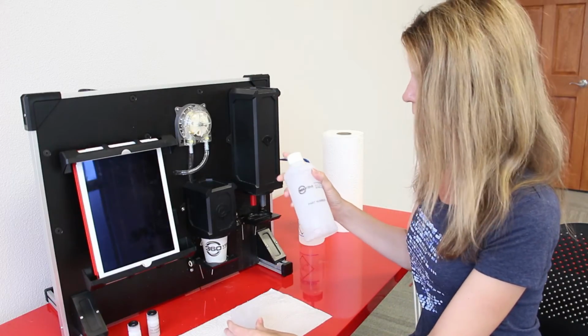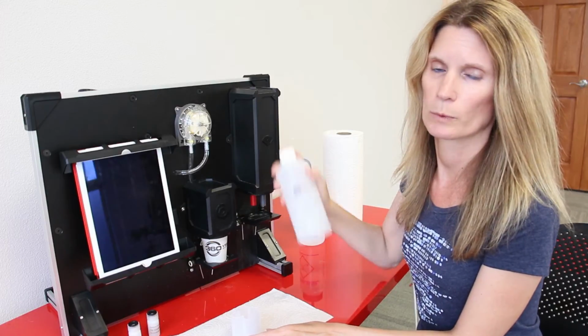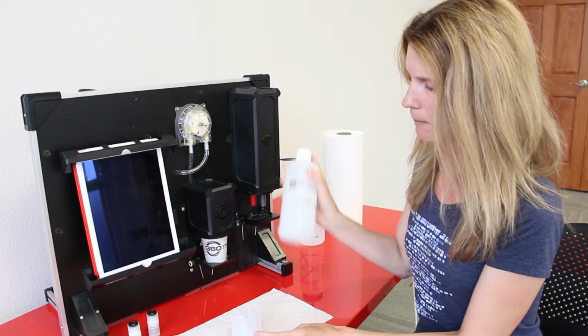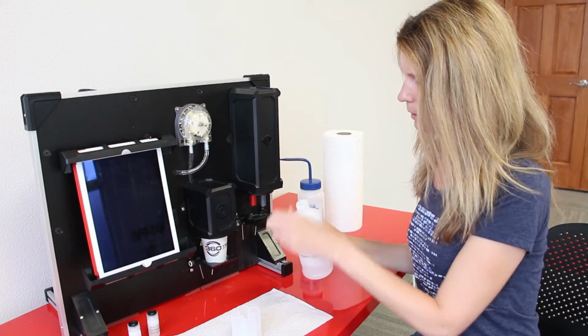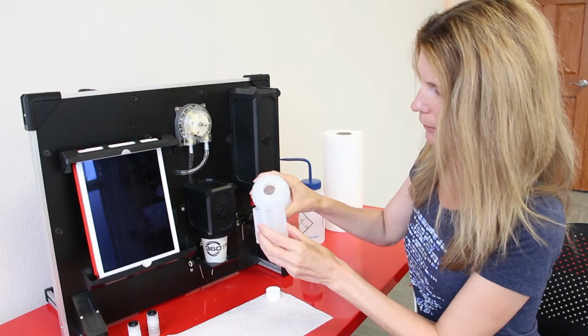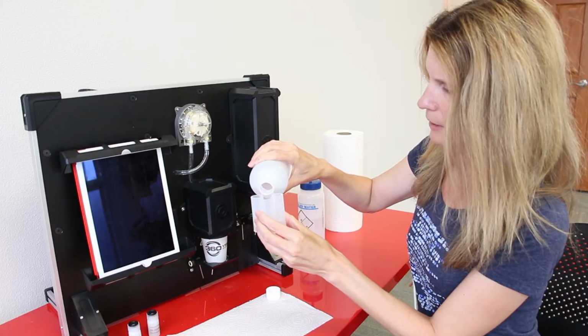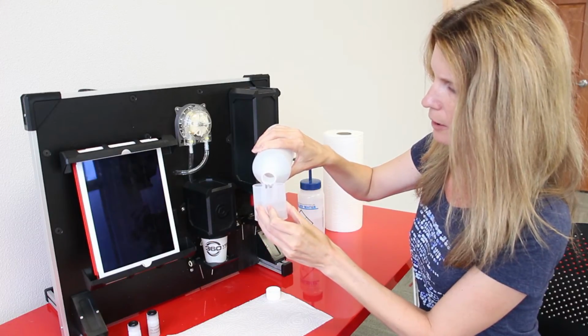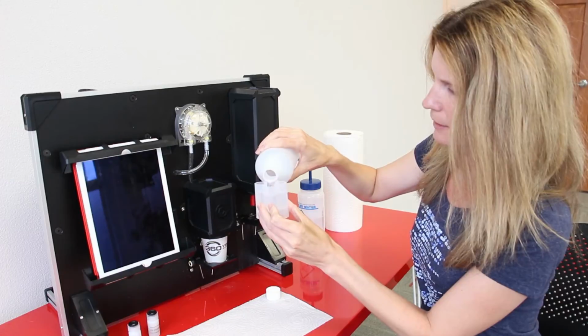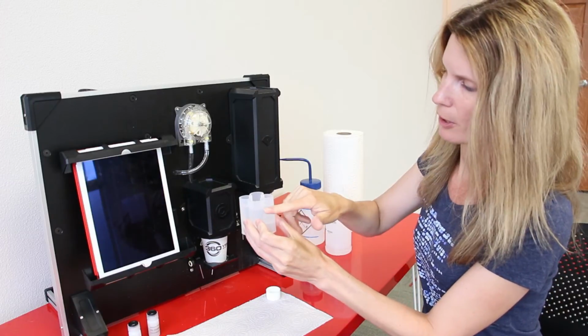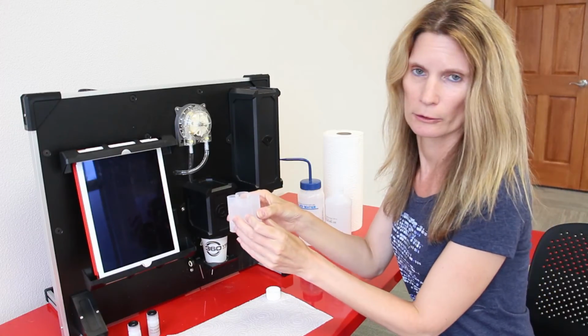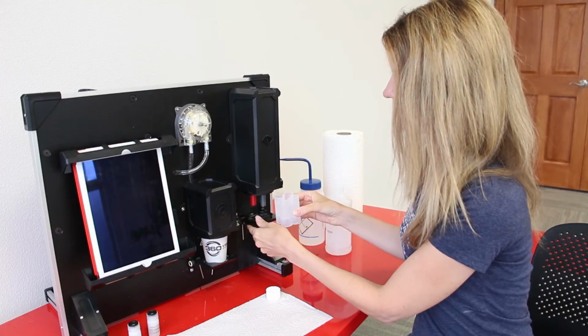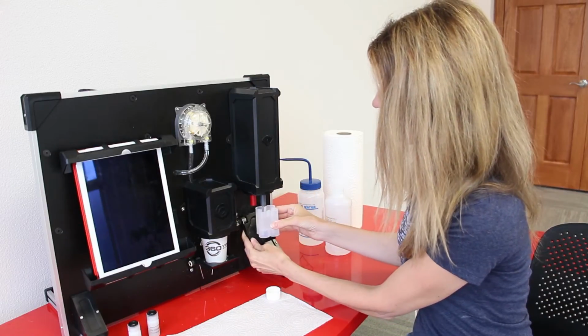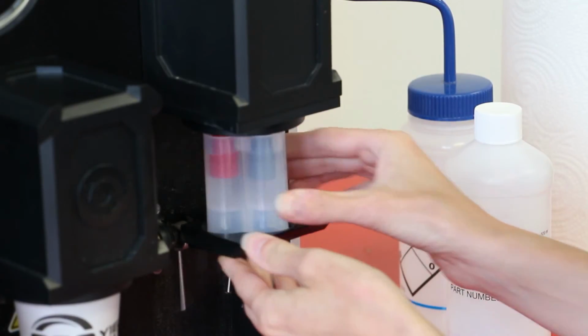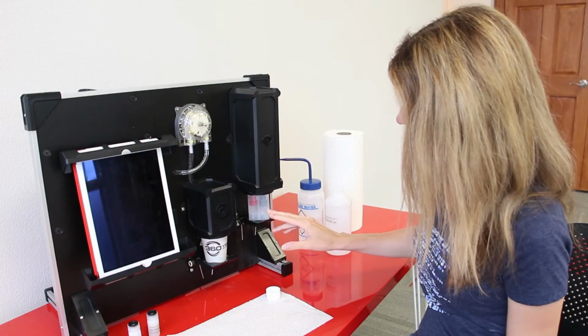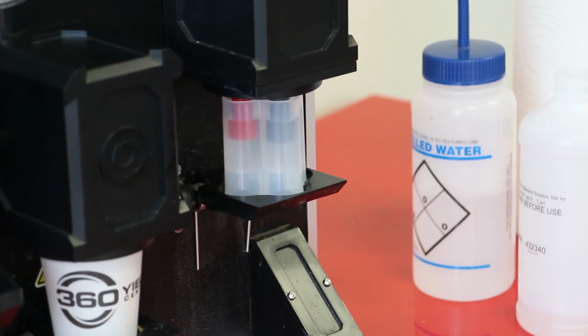And now what we do is we take our standard solution, we give it a good shake just to mix things up. And then we're going to pour it about up to the 3/4 line here. There's a thin manufacturing line on here that you can see, and if you fill it up to about this far right up, that will allow you plenty of standard solution in there so that your sensors can soak. So we're going to put it on here. We're just going to let that set on the sensor shelf. Have both our nitrate sensor and our red reference electrode sitting in that to soak.